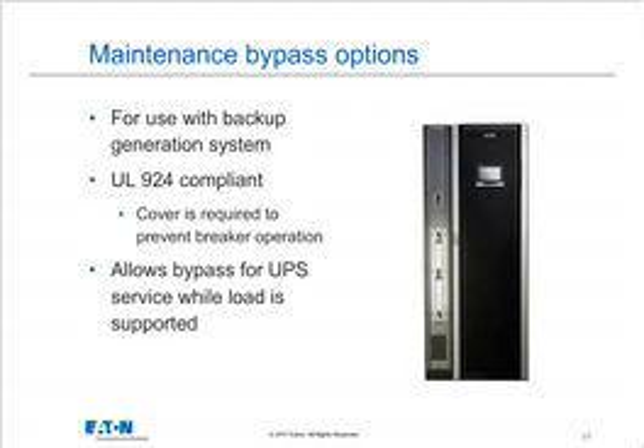So a maintenance bypass can be UL 924 compliant as an option for the UPS. It allows service while the load continues to be supported. It even allows the load to be supported while the UPS is exchanged for a new one, for example. So those are good reasons to deploy a maintenance bypass, otherwise known as a wraparound bypass, with a UPS for this application. So it's recommended but not required.